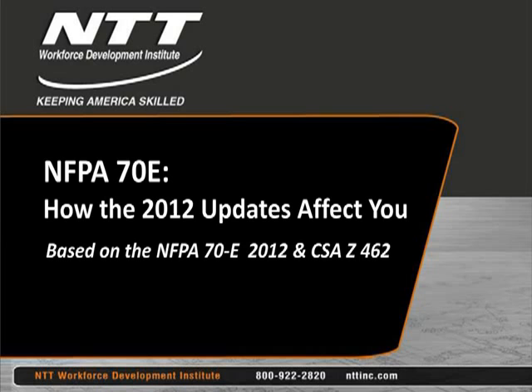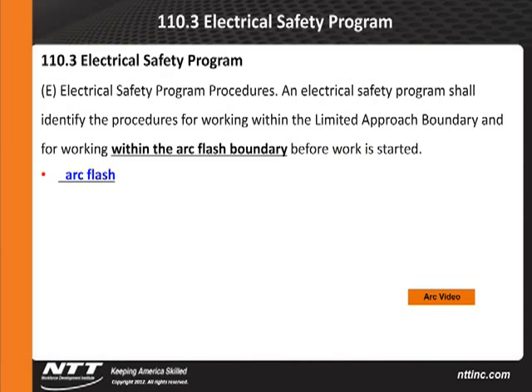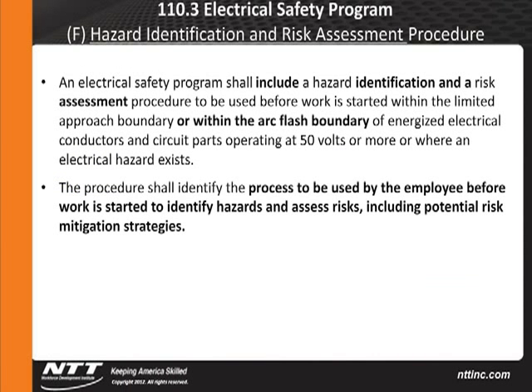So as we go on here then, what do we have to do? What kind of a program do we have to have in place? And again, I don't have time to cover everything that's in here, but it says an electrical safety program shall include a hazard identification and a risk assessment procedure to be used before work is started within the limited approach boundary or within the arc flash boundary of energized electrical conductors and circuit parts operating at 50 volts or more where electrical hazard exists. This language is going to have a major impact on many of you sitting here.